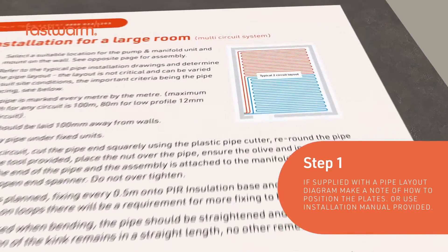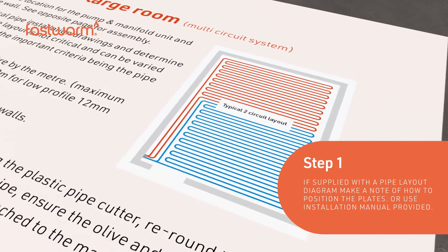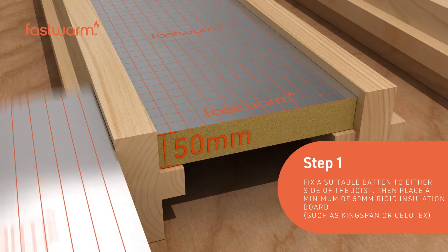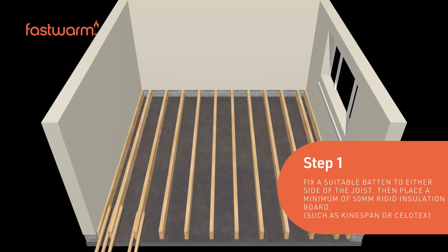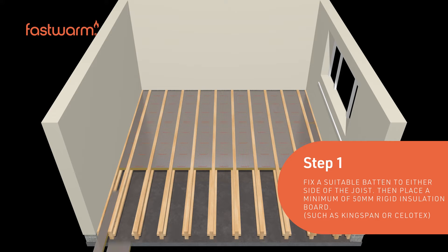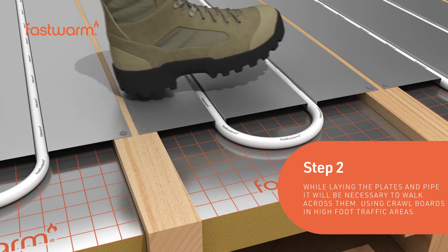If supplied with a pipe layout diagram, make a note of how to position the plates. Alternatively, refer to the installation manual provided. Fix a suitable batten to either side of the joist, then place a rigid insulation board onto the batten, such as Kingspan or Celotex. This needs to be a minimum of 50 millimeters thick.